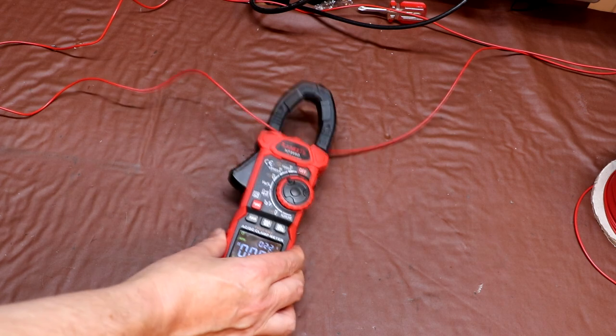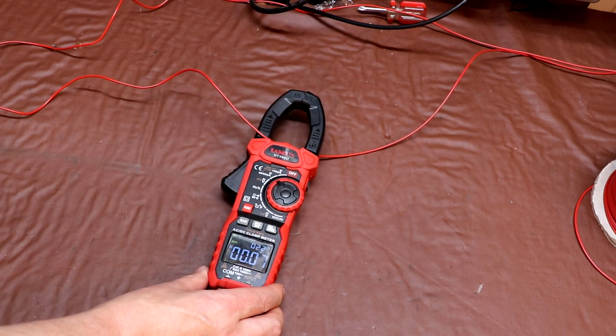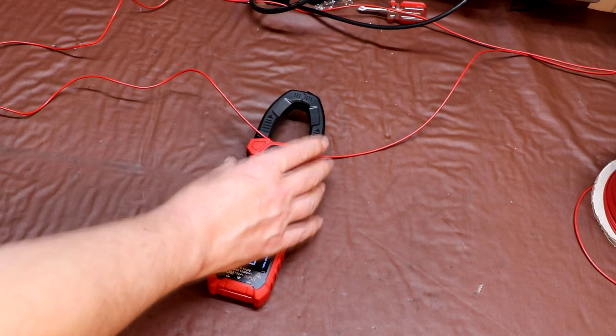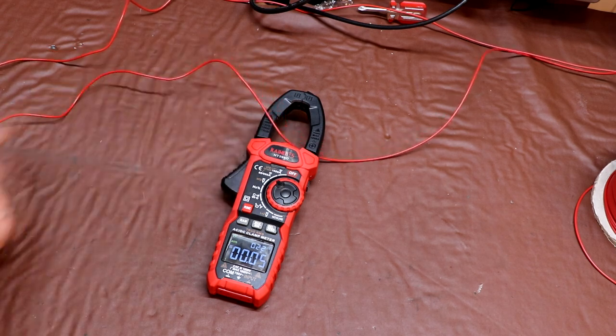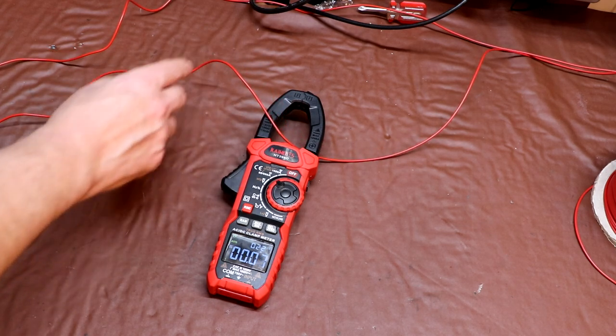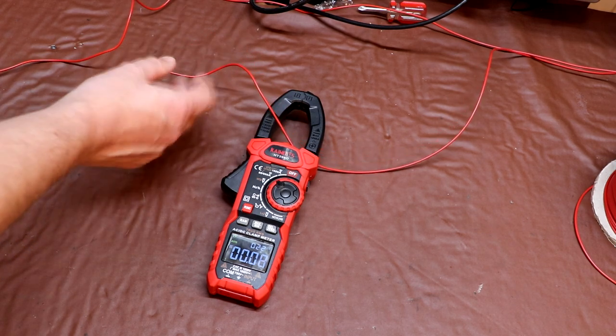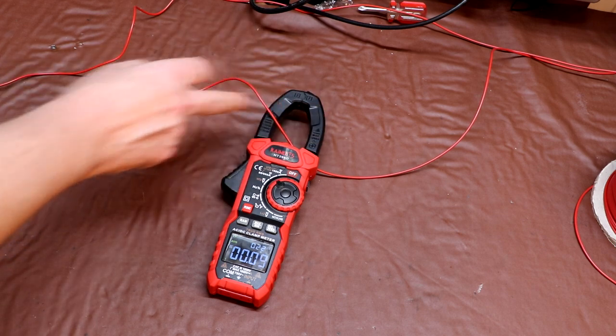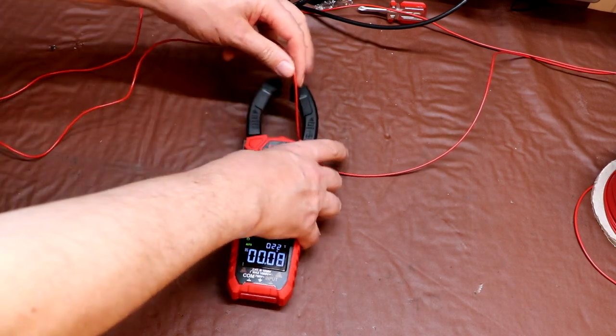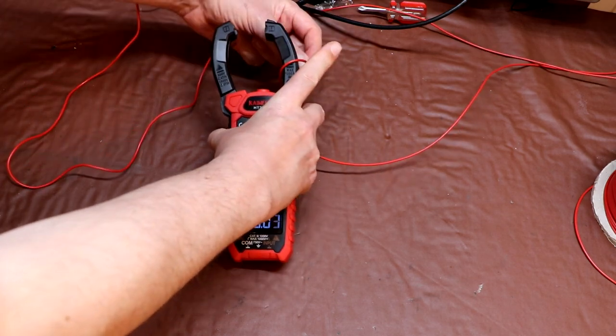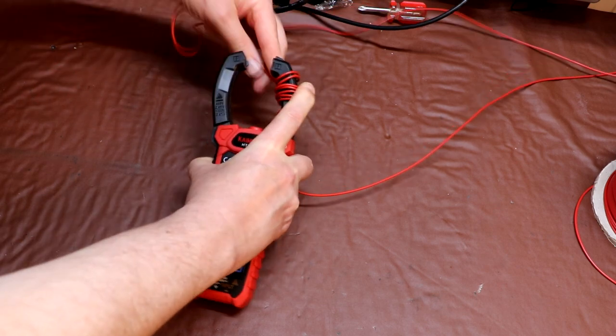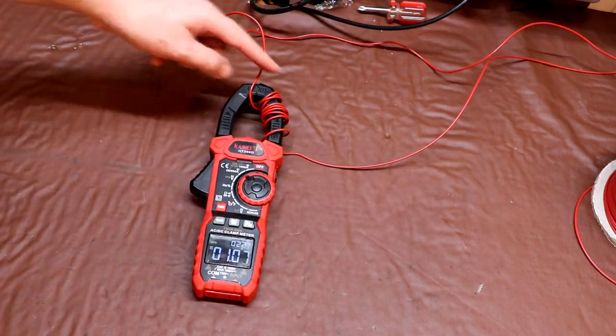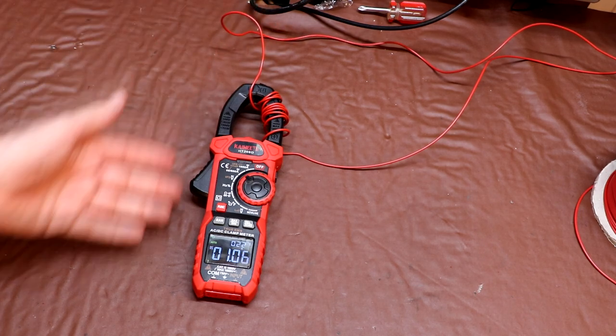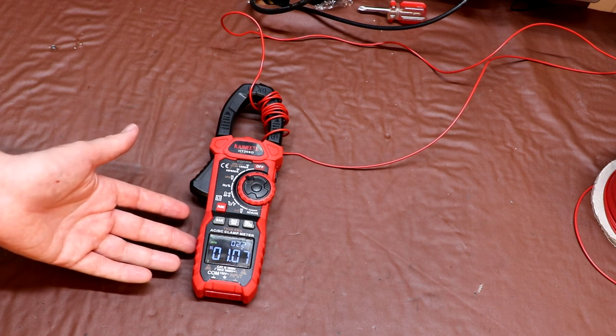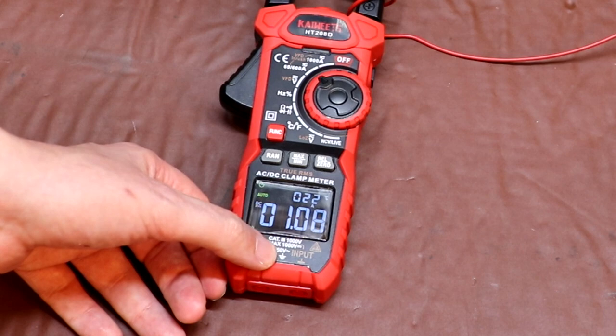Now if you have a clamp meter but you're struggling to measure some very low currents, there's a little trick we can employ to make the meter more sensitive. The clamp meter is effectively measuring the magnetic field given off by our wire here. So we can increase the level of that magnetic field by putting more turns of wire around the clamp jaws. So let me do that. We've got 1 turn at the moment, so I'm going to open up the jaws. 1, 2, 8, 9 and 10. So rather than having 1 turn of wire, we've now got 10 turns. Effectively we've increased the sensitivity of our meter by a factor of 10. So rather than reading 0.1 of an amp, it's actually reading 1 amp now.